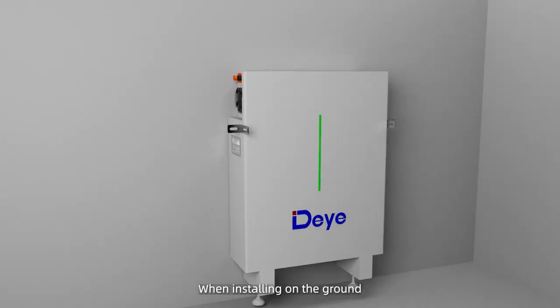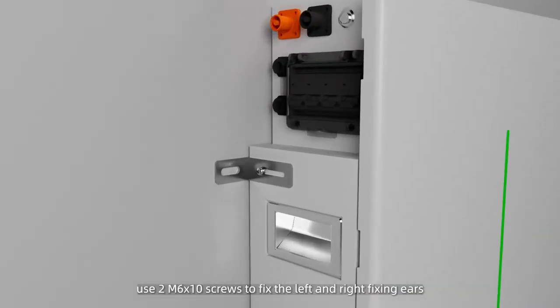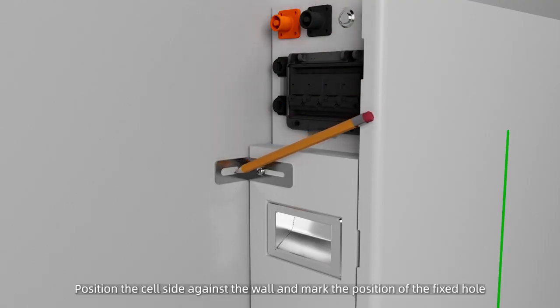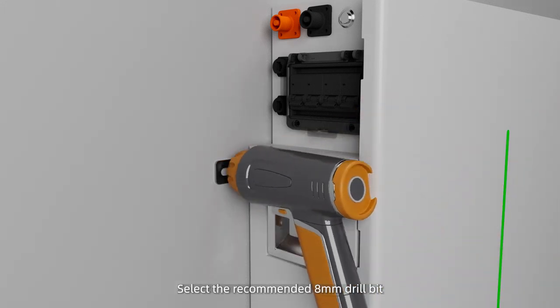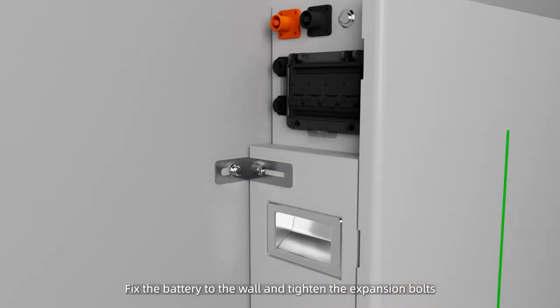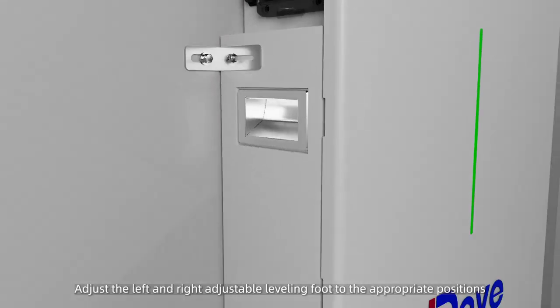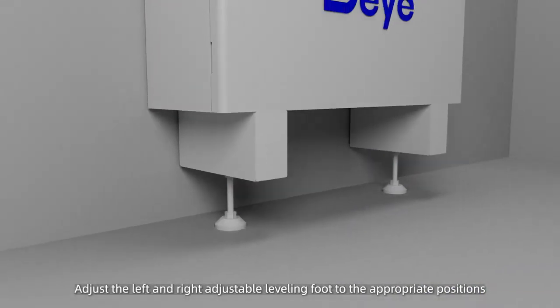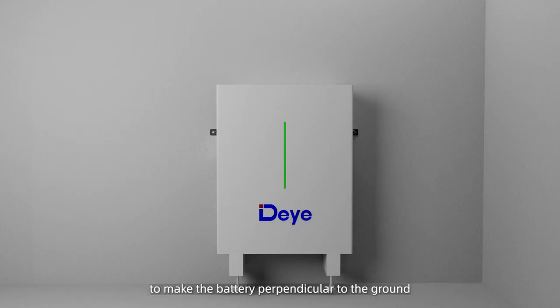When installing on the ground, use 2 M6x10 screws to fix the left and right fixing ears on both sides of the battery. Position the cell side against the wall and mark the position of the fixed hole. Select the recommended 8mm drill bit and drill 2 holes in the wall with a depth of 100 to 110 millimeters. Fix the battery to the wall and tighten the expansion bolts. Adjust the left and right adjustable leveling foot to the appropriate positions to make the battery perpendicular to the ground.